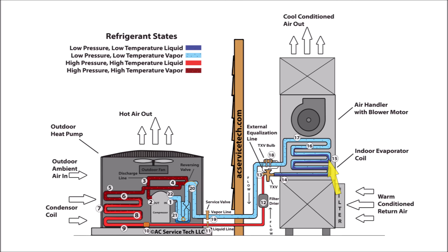In step fifteen, you have the refrigerant in the saturated state where both liquid and vapor exist at the same time. The refrigerant continues to absorb heat from the evaporator but does not change in temperature. In step sixteen, the refrigerant absorbs enough heat energy in the saturated state to turn into a complete vapor. Once it turns into a complete vapor, it continues to absorb heat but now increases in temperature. Any increase in temperature in the vapor state is called superheat.